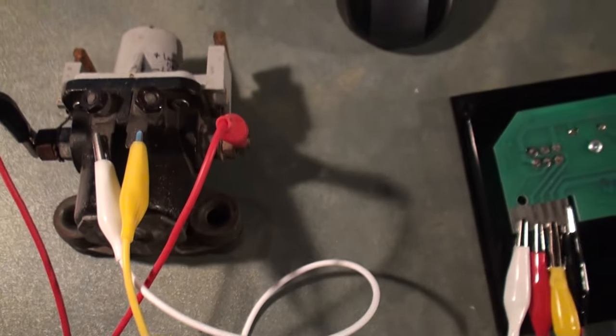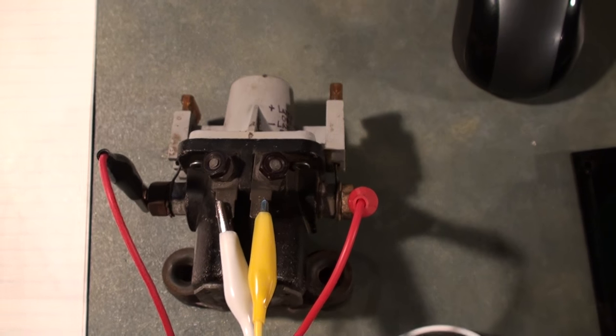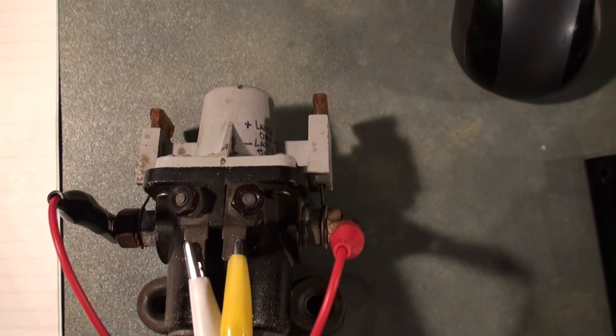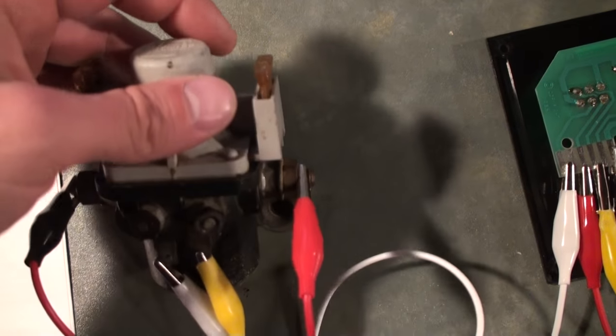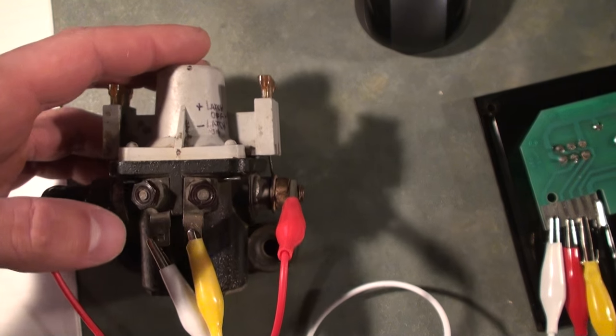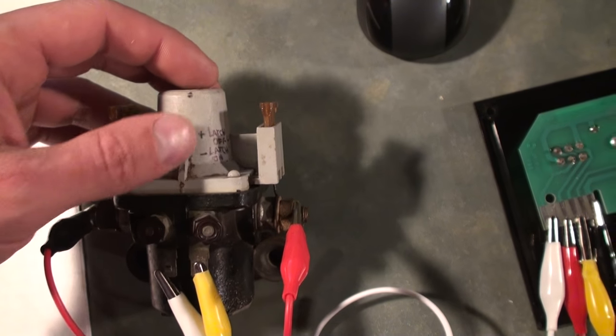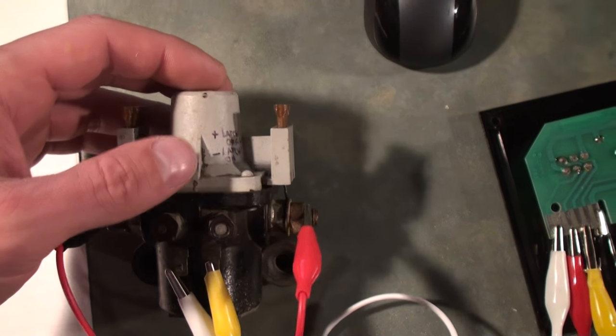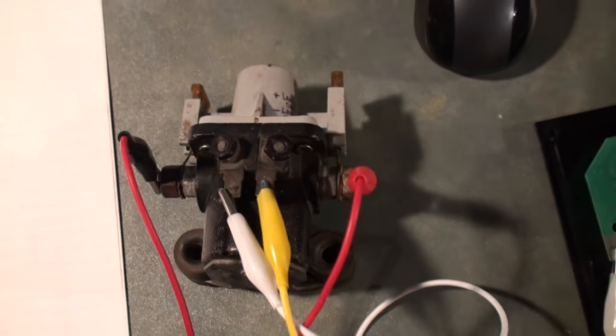And the reason for that is, of course, this is a latching relay. It does not require constant power to keep the contacts connected. And if you were to open one of these up, you would see how that works. Just got a little pin. That's what this structure here is on top. It's got this little pin that when you turn it on, it sort of jams the switch in the down position. And when you reverse the polarity, because the polarity is reversed and this pin is magnetic, it pushes it out of the way. And since the plunger is on a spring, it forces it back up.